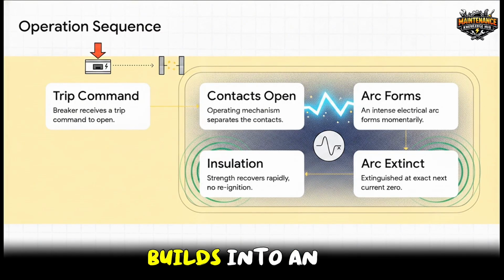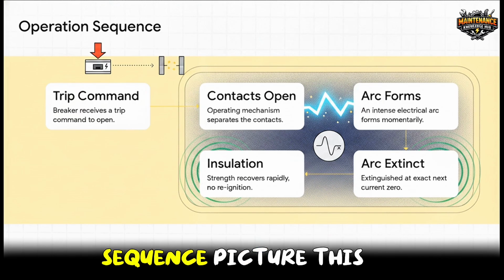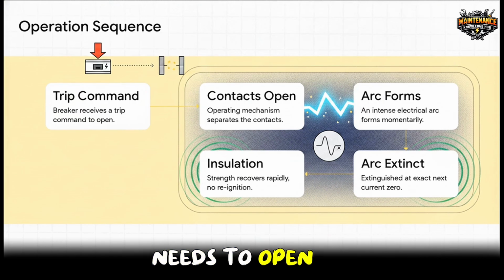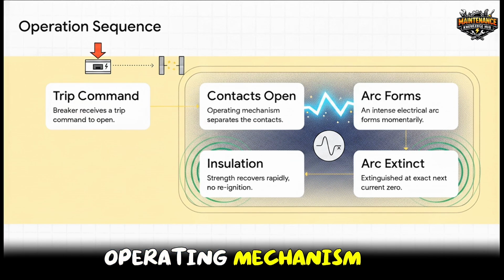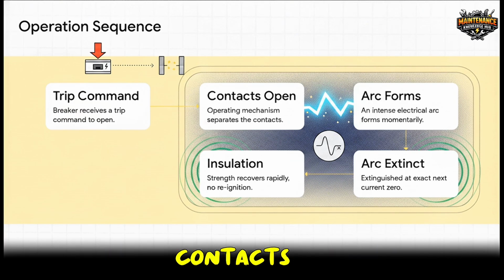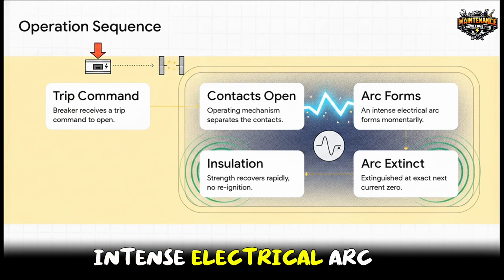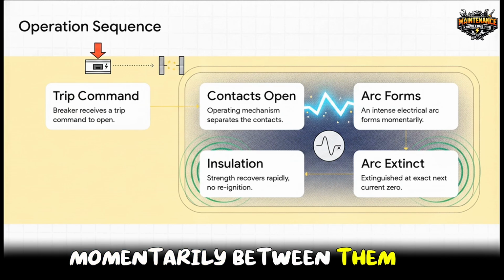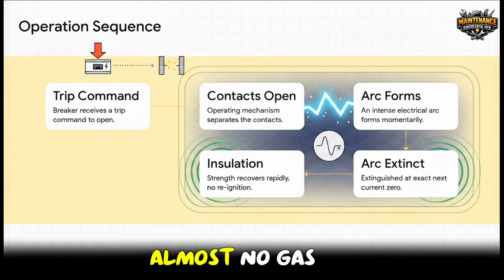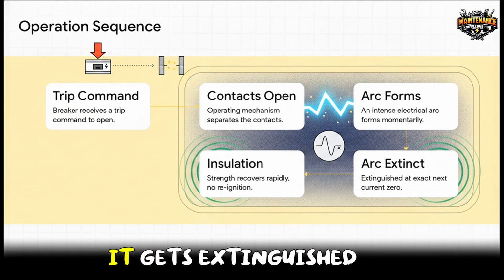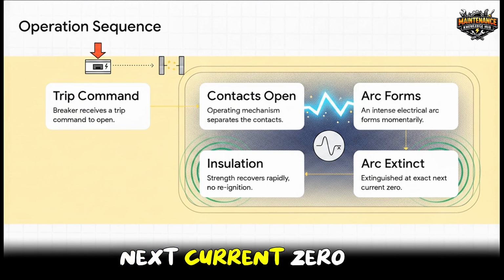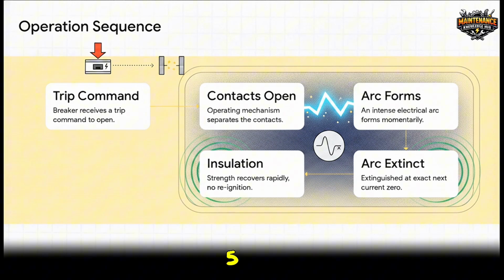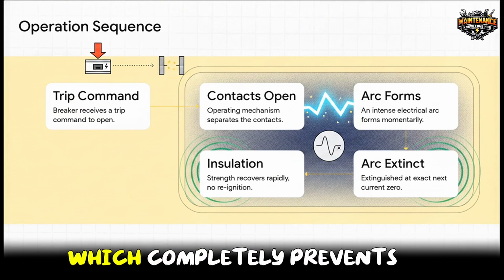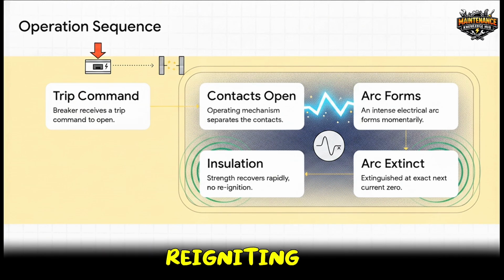So let's see how this all builds into an actual action sequence. Picture this. When the breaker needs to open, step 1, it receives a trip command. Step 2, the operating mechanism forcefully separates the moving and fixed contacts. Step 3, an intense electrical arc forms momentarily between them. Step 4, because there is almost no gas to sustain that arc inside the vacuum, it gets extinguished at the exact next current 0. And finally, step 5, the insulation strength recovers rapidly, which completely prevents the arc from reigniting. Honestly, it happens faster than you can blink.